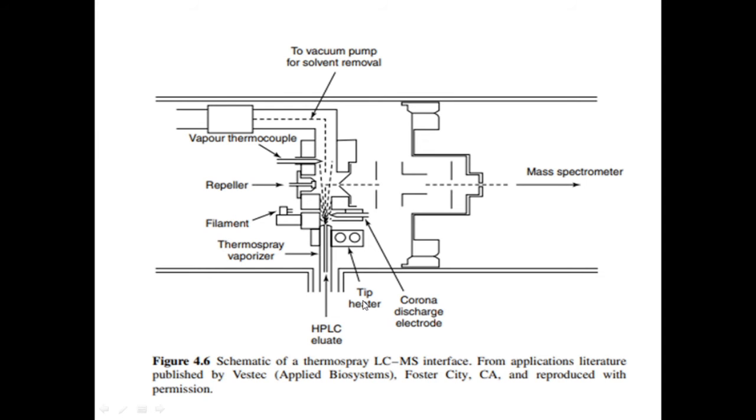Control of the vaporization process, that is, the temperature of the capillary, is of crucial importance. Optimum performance is obtained with around 95% vaporization of the liquid stream. Too much heat results in vaporization occurring within the capillary with deposition of analyte, and if operation of the interface under this condition is continued for any length of time, blockage of the capillary.